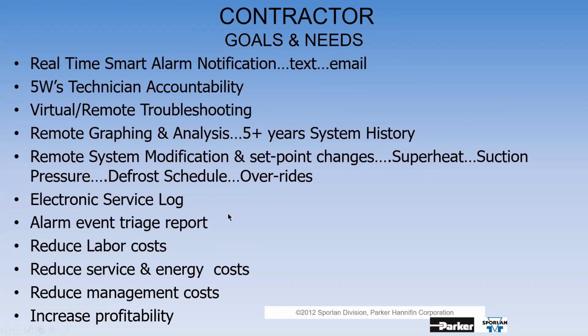It allows you to do remote system modification—set point changes, superheat, suction pressure, defrost schedule changes, overriding a compressor or a fan. There's also an electronic service log, so it's not just the oil-soaked loose-leaf binder in the mechanical room. We always tell people to use the electronic service log so you can tell what someone did remotely—you don't actually have to be there.